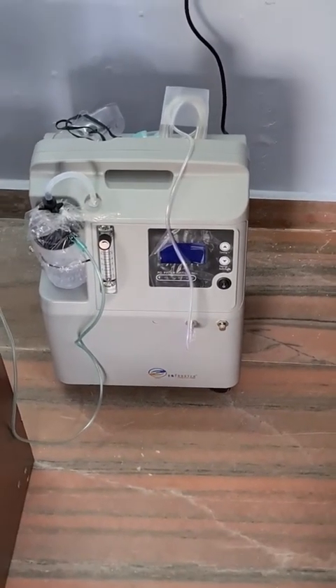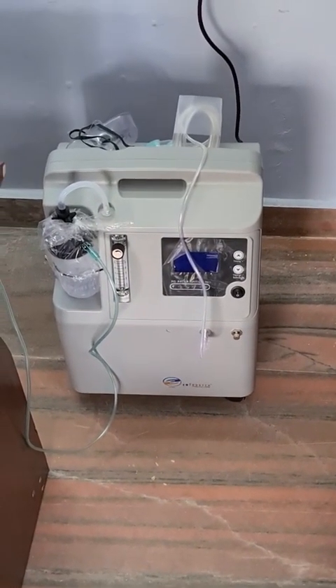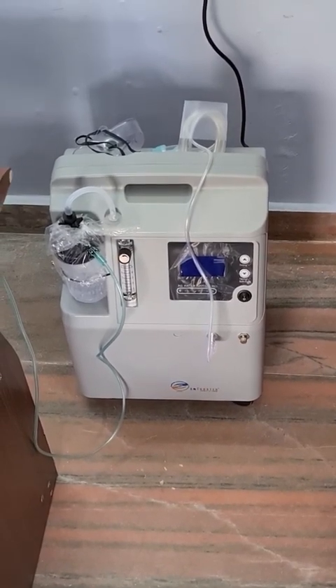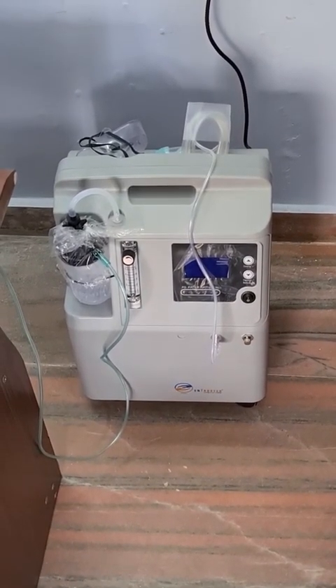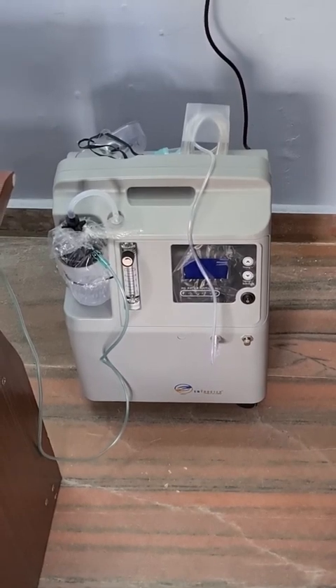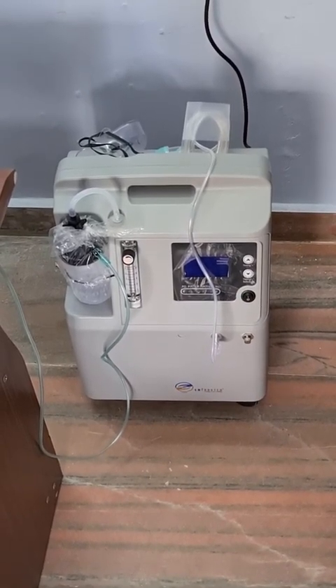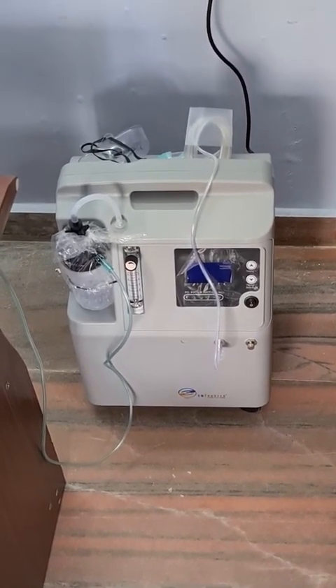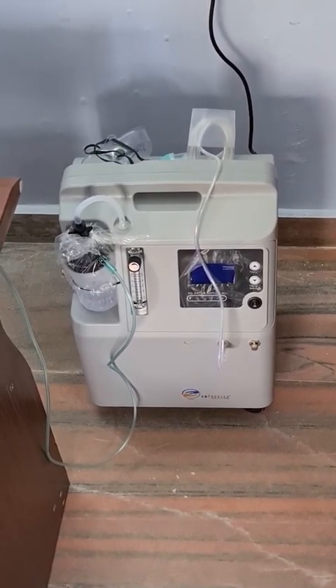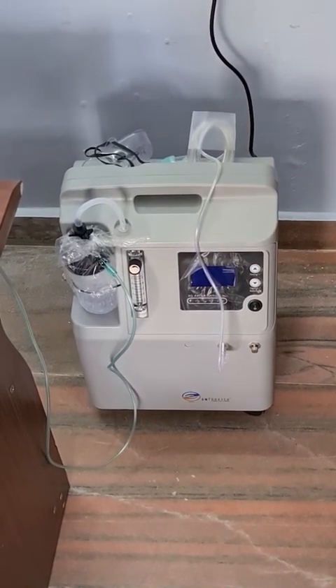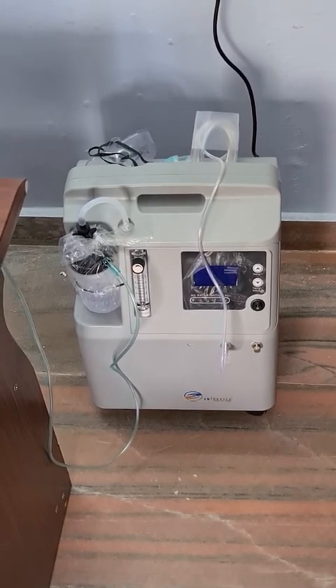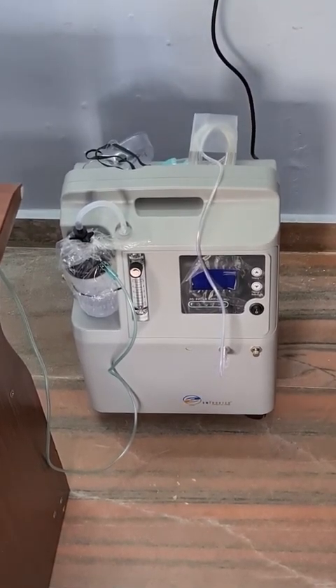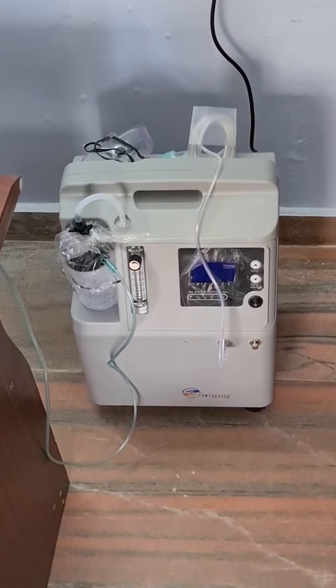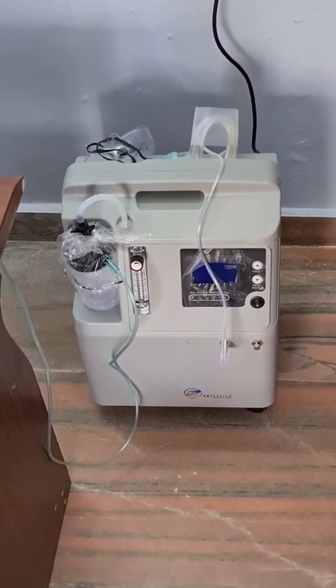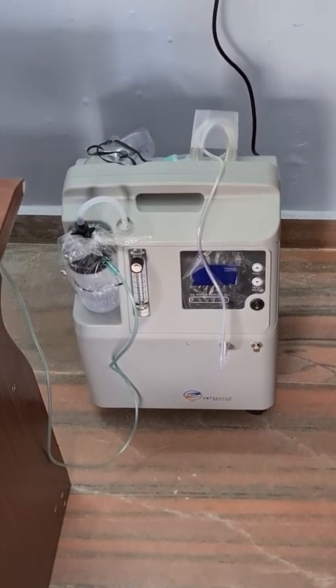Also, another important point: when people purchase an oxygen concentrator, a general question they have is whether it can be run for 24 hours continuously. The simple answer is that you can, but it is not advised, because that will bring down the life of the equipment. A concentrator is also a medical device which needs some break intermittently. So the correct advice for a longer lifetime is that once in every 8 hours, give the machine a break of at least 15 to 30 minutes.